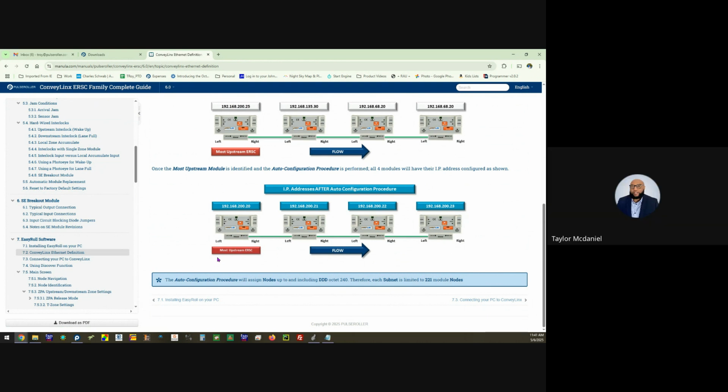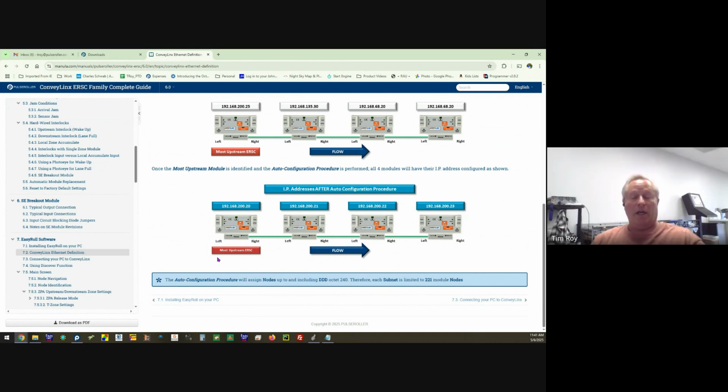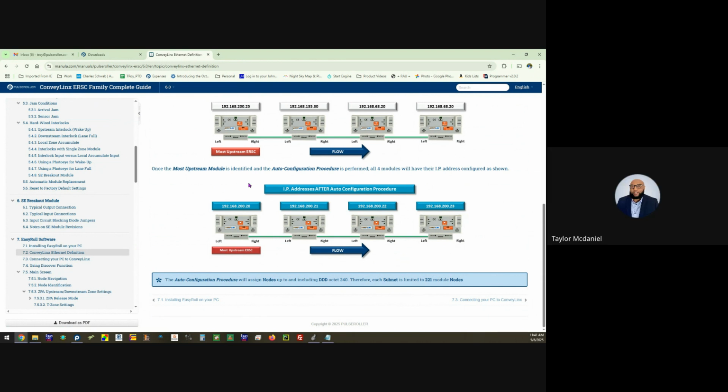Default is 200 milliseconds, but we can poll faster. That is correct. Actually, what I've noticed with the EDS file, it defaults to 50. 50 RPI. Yes. And then you can adjust it up or down. All right, I've got to keep that in mind because we got them stacked on a network, and I don't think we exceeded 128 per that EN2T, but we were having comms issues. I think everybody was set on the same default RPI, so the PLC was probably polling every 200 milliseconds, saying give me updated information, but give me everybody's information at one time.